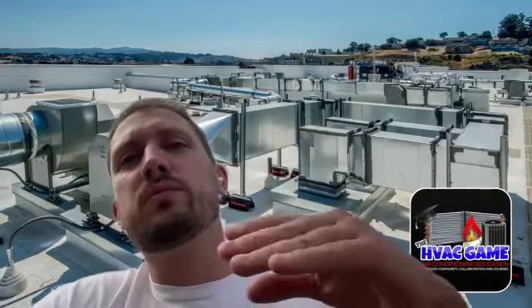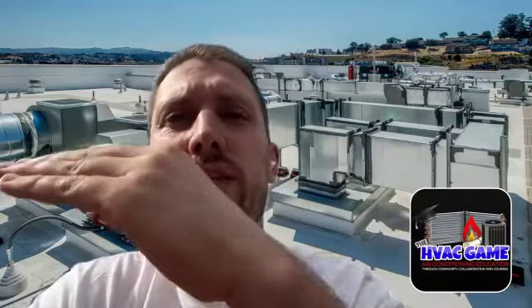So you have saturated refrigerant, with refrigerant existing as a vapor and a liquid at the same time. Now, if you want to understand superheat, think of the refrigerant in the evaporator. It's moving through the evaporator coil, so you're picking up more and more heat, and more and more of the liquid refrigerant evaporates and turns into a vapor. Now you get to the point where all of your liquid refrigerant has evaporated. So now you're at 100% vapor, but you're not past all of the evaporator coil yet, so you're still picking up heat. So what happens after that? That is what is superheat.